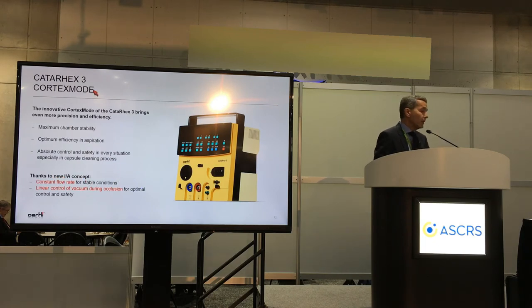In the IA aspect of this machine, we have the cortex mode. What the cortex mode does is give us absolute control and safety in every situation, especially in capsule cleaning processes. We can program it so we have a constant flow rate for stable conditions, and then a linear control of vacuum during occlusion for optimal control and safety.